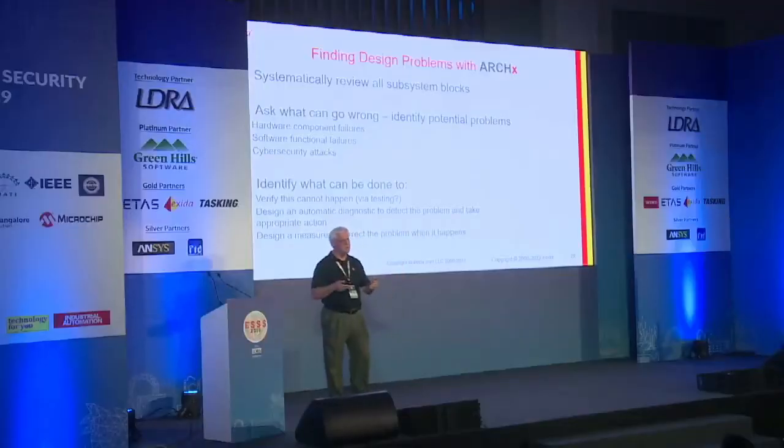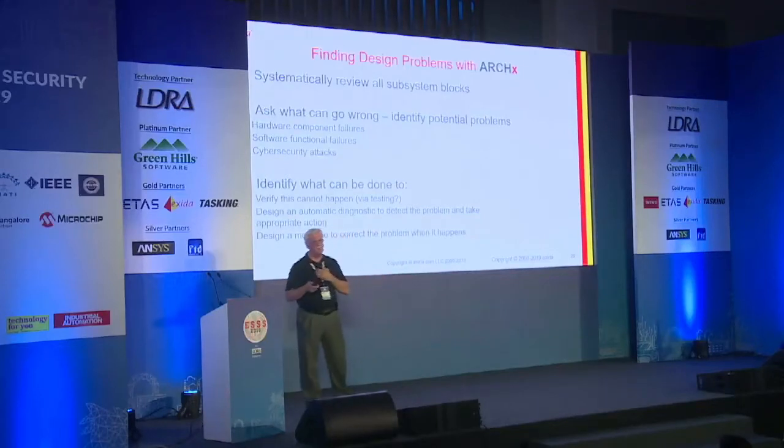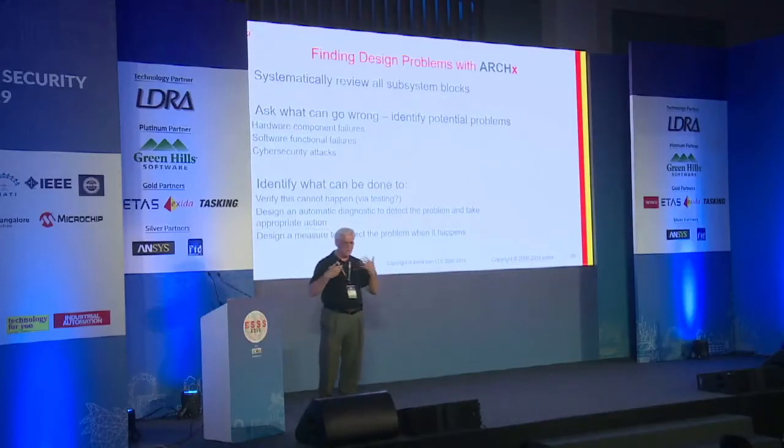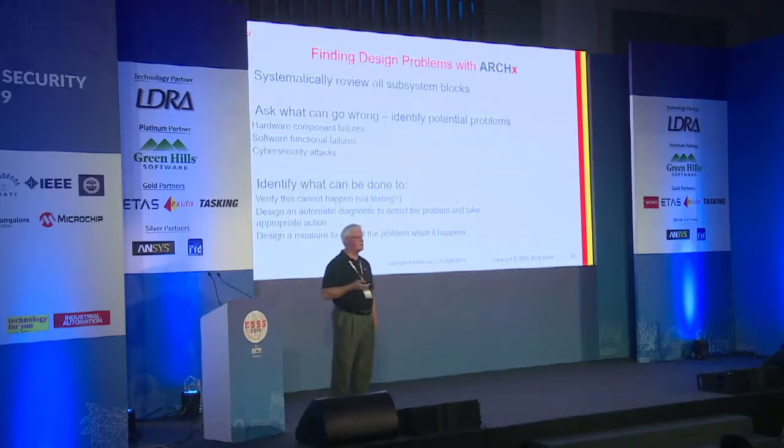An important part of the process of developing equipment is having a good, solid design in place. And one of the things that you do once you partition your product into its various components, you establish a high-level architecture, which then you subdivide into hardware and software components, is doing a hazard and effect study on that architecture.